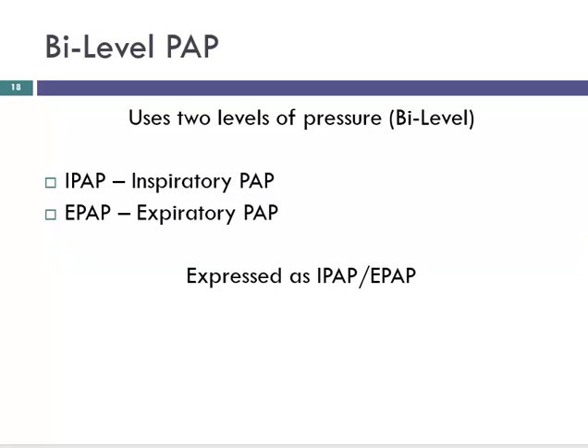Another modality that we can try is known as bi-level PAP, whereas CPAP is continuous. It's one single pressure, same pressure you're breathing in, you're breathing out against. BiPAP uses 2 pressures. We have an inspiratory pressure and an expiratory pressure, and you'll see it expressed as IPAP over EPAP. So, 8/4, 8 is the inspiratory, 4 is the expiratory.